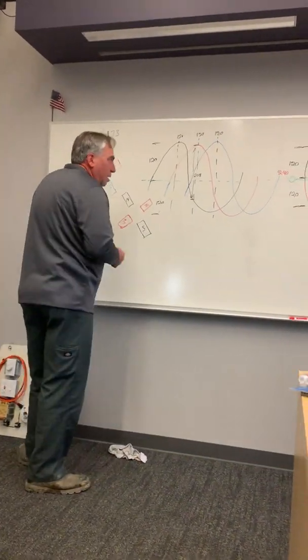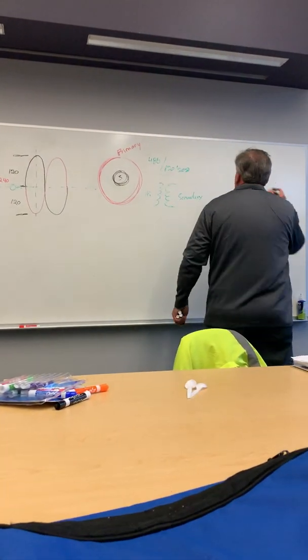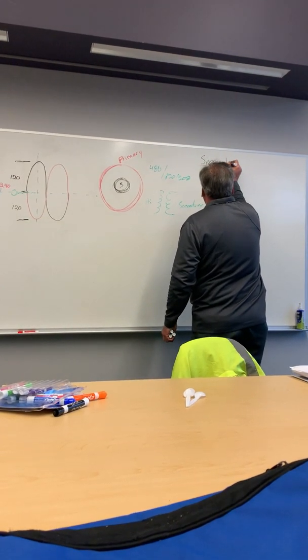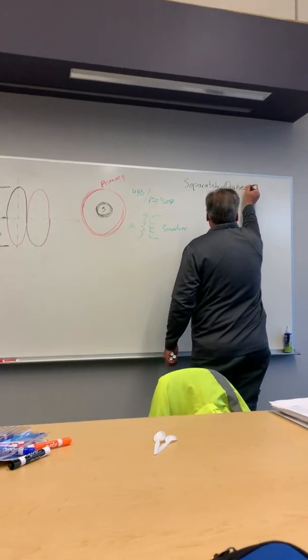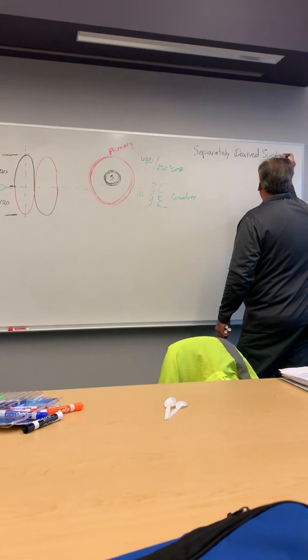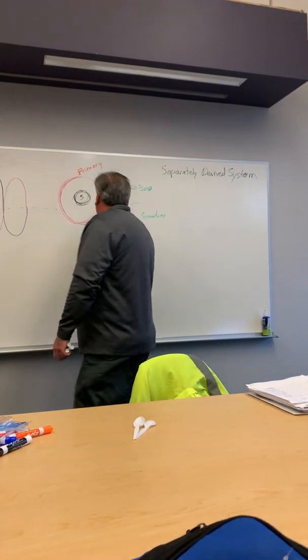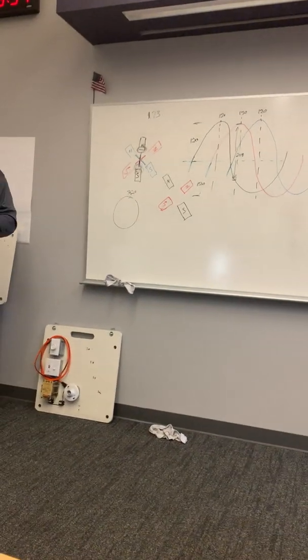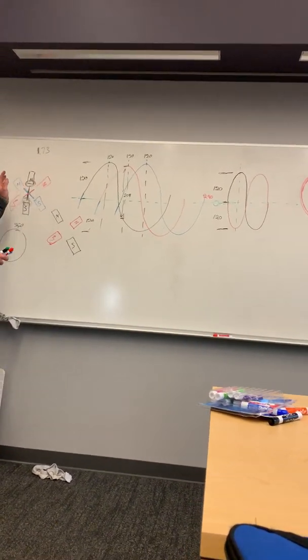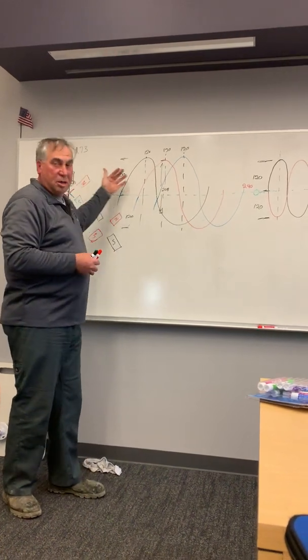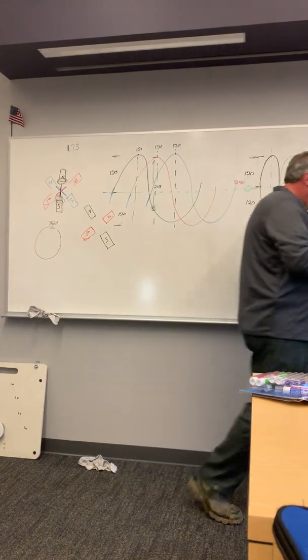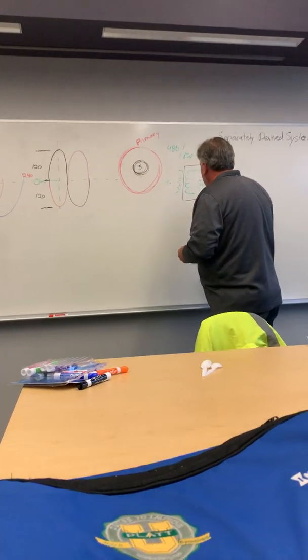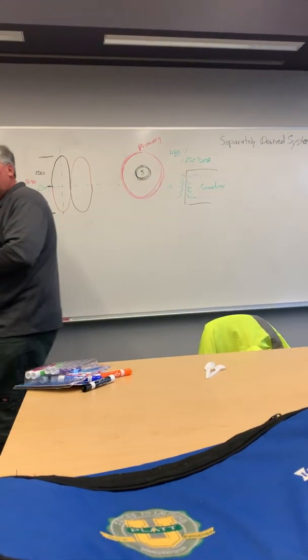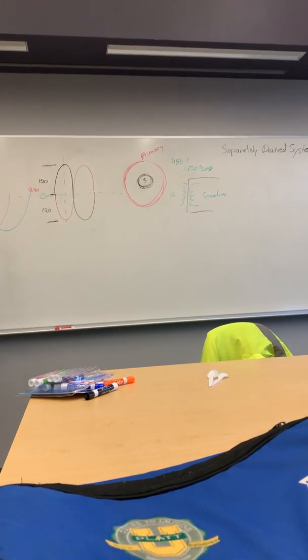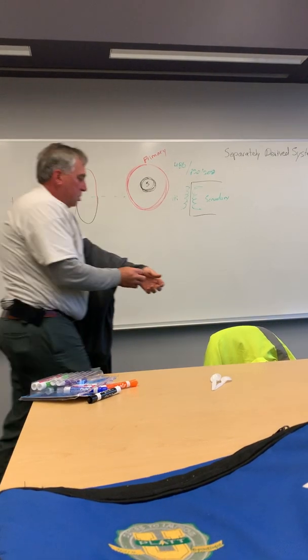And that's creating the secondary voltage, which I like to call - and I got him on this one - a separately derived system. That's what a transformer is. When the book refers to a separately derived system, it's either a generator or a transformer. Otherwise, if it's coming from a source and feeding it connected from the service, that's fine. But here you're taking the service and running it through this part, which is not connected to any other part of the building power - the secondary you're creating is separately derived.